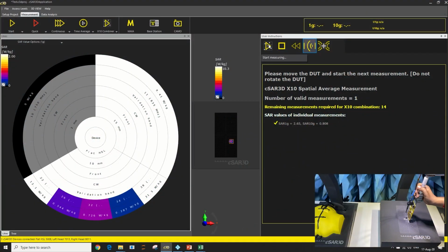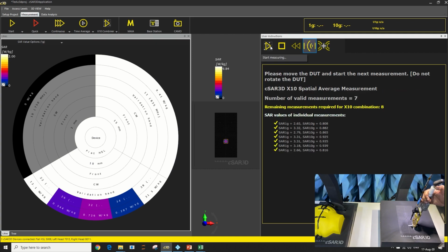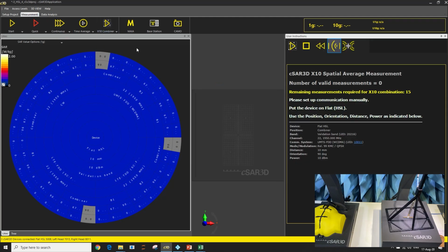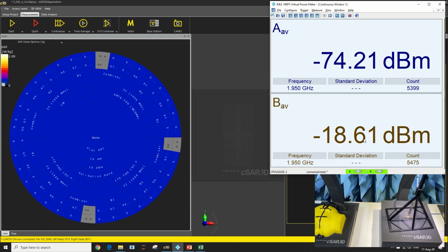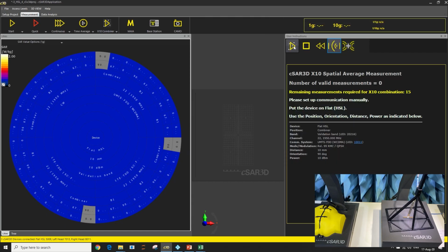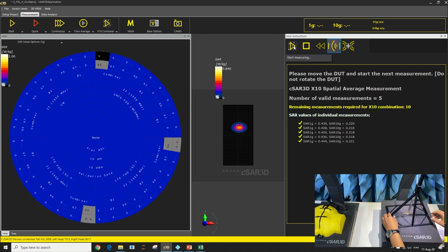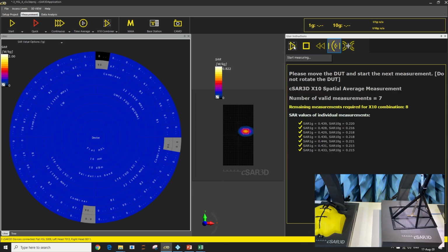I would expect improved accuracy for the VPIFA sources and for the frequencies above 5 GHz with the new X10 Combiner feature, but hardly any improvements for the other sources as CSAR 3D is already exceptionally accurate for sources with a wide distribution, thanks to the very good isotropy and calibration of the system.